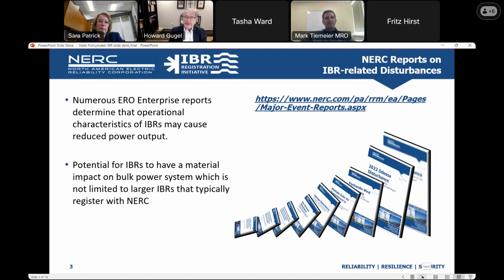Over the last 6+ years, we've seen an increasing number of events that have involved inverter-based resources. And many of those are involving resources that are connected at lower voltages than what we had traditionally looked at for bulk electric system. They are connected at lower megawatt thresholds, so smaller units connected together, and then also at smaller levels. But what we are seeing is that they have common mode reactions to events. So whether it's faults that occur on the system or changes that occur due to load problems or generation problems, we will see multiple inverter-based resources have the same reaction on the system.